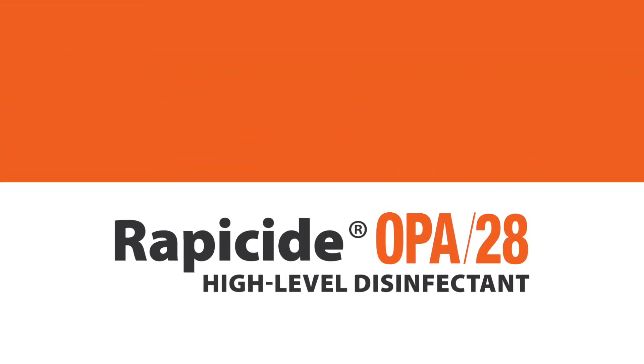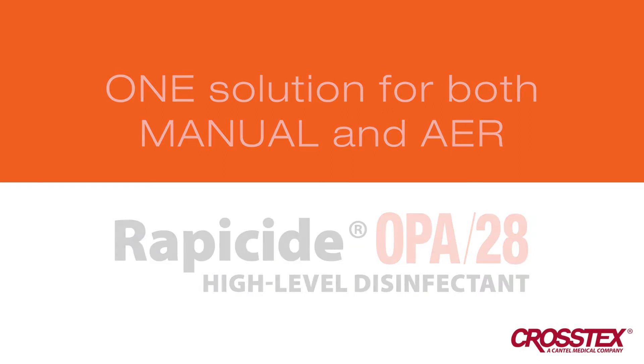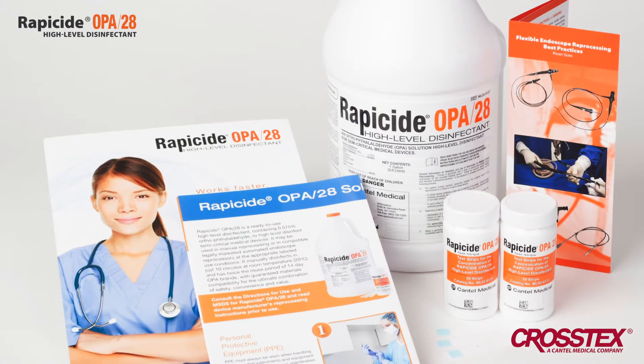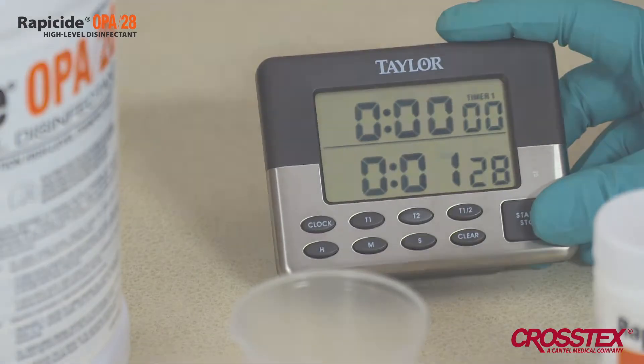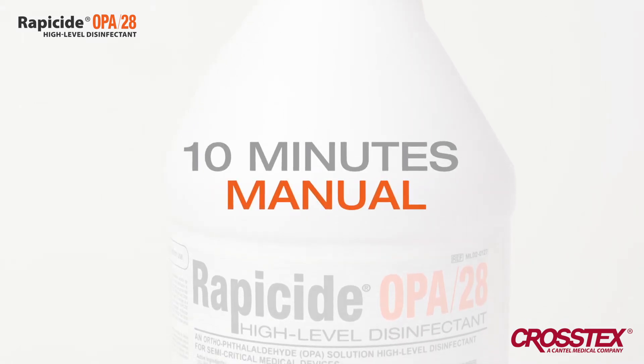Cut your disinfection solution in half with Rapicide OPA28 high-level disinfectant. Rapicide is the one solution you need for both manual and AER disinfection. Rapicide offers faster disinfection than any OPA or glutaraldehyde on the market today — just 5 minutes for automatic disinfection and 10 minutes for manual.